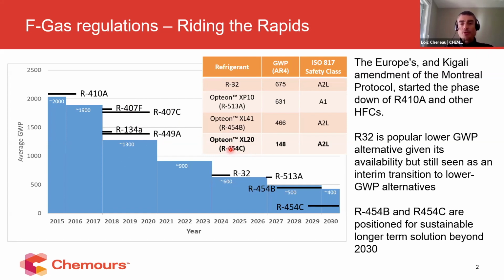Now, there is also a good thing when we talk about the 454C refrigerant with regard to the discharge temperature, because if, for instance, this product is being considered and adopted from a 410A refrigerant system, there will be a much lower discharge temperature. That is also interesting in some cases to increase the lifetime that you can expect, because you are in a much less stringent envelope of use for the compressors. And this is why this product can be of interest, coming from the 410A refrigerant HFC, but of course also having to redesign the equipment.